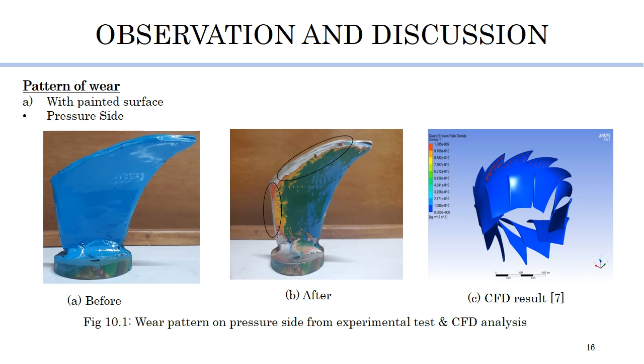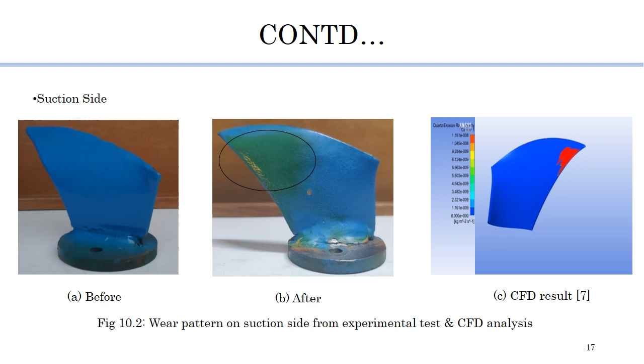At the suction side, the erosion pattern on the outlet region of the suction side might have been because of the turbine being of low head. Removal of the paint near the base was seen due to the vortex created by the bolt head. The pattern of wear in the suction side was also found to be similar to that of the result from the CFD analysis.